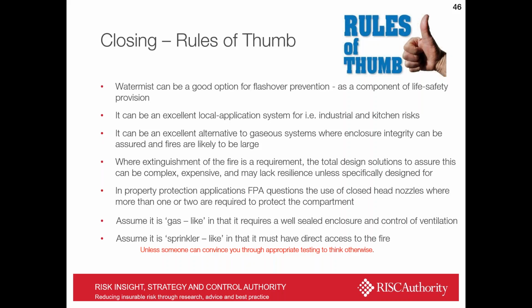It can be an excellent local application system for industrial and kitchen type risks. It can be an excellent alternative to gaseous systems where enclosure integrity can be assured and fires are likely to be large. Where extinguishment of the fire is a requirement, the total design solutions to assure this, we know, can be complex, expensive, and may lack resilience unless specifically designed for. And I guess this is the large area where we see competition between sprinklers and water mist systems. When you do start to fulfill the requirements of building regulations and seek not only equivalency in terms of performance, but resilience, we can very quickly see that any perceived cost saving can quickly get gobbled up while trying to do the full and proper job.